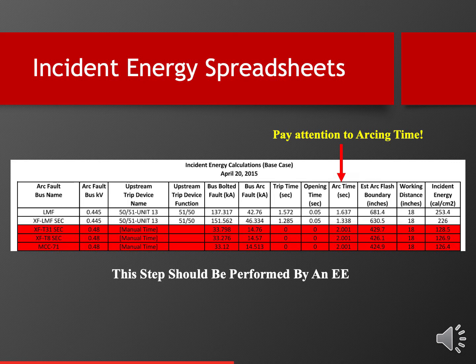Their logic is that most arcs last less than 2 seconds, which is true, they also think that a person wouldn't stay in an arc for longer than 2 seconds. And only somebody who doesn't work for a living could come up with that idea, because the truth of the matter is that when you get involved in an arc flash, by the time you realize what happened, it's over. So here's the deal, and I've highlighted it in red for my customer. Anytime the arcing time is 2.001 seconds, what that means is we have stopped calculating incident energy at 2 seconds. It doesn't mean the arc goes out in 2 seconds.